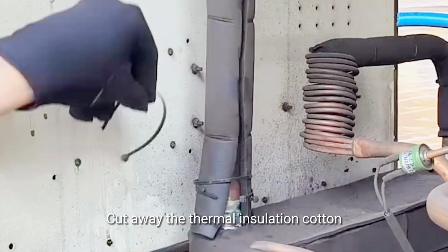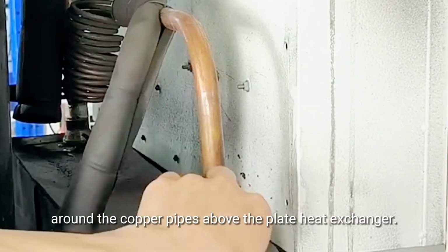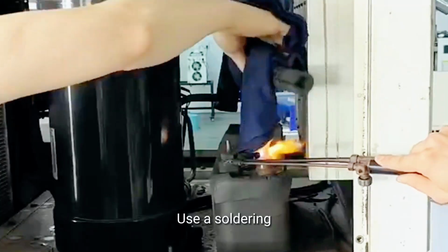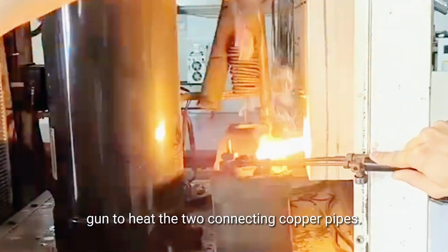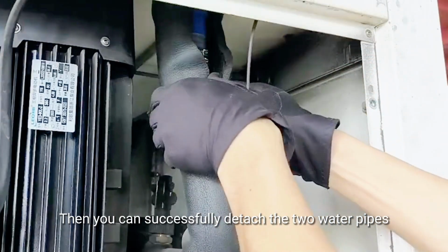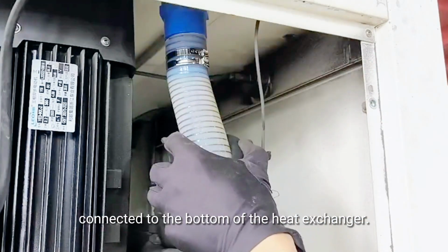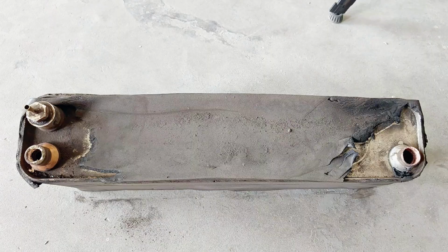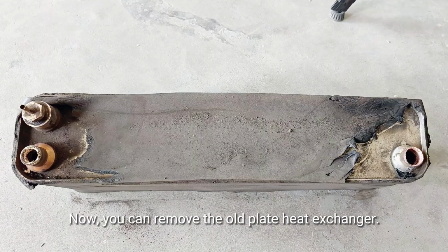Cut away the thermal insulation cotton around the copper pipes above the plate heat exchanger. Use a soldering gun to heat the two connecting copper pipes, then detach the two water pipes connected to the bottom of the heat exchanger. Now you can remove the old plate heat exchanger.